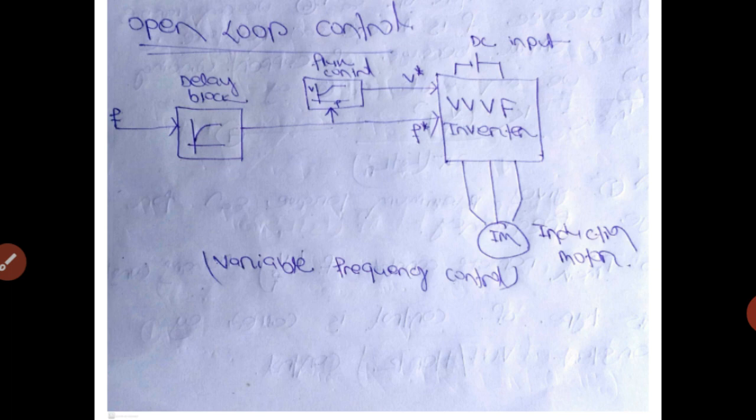But when we reach the rated frequency, we also reach the rated voltage. Beyond the rated frequency or rated voltage, voltage is not increased further, because the induction motor has some insulation, and if we increase the voltage beyond the rated voltage, it will be stressed. So we cannot increase beyond the rated voltage.